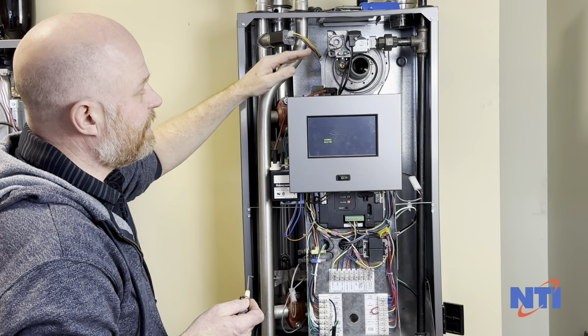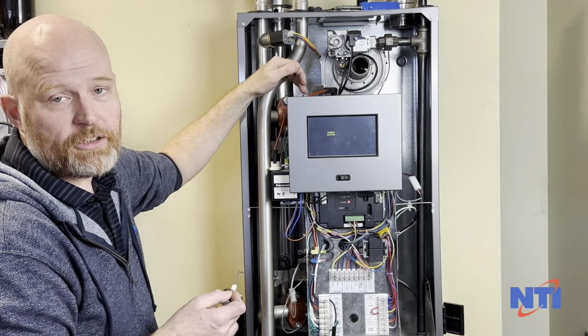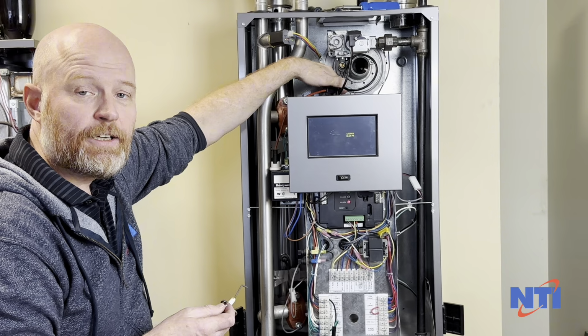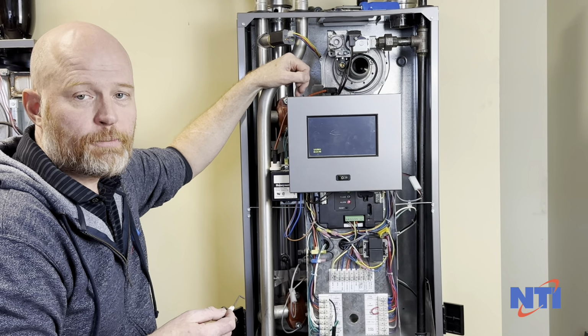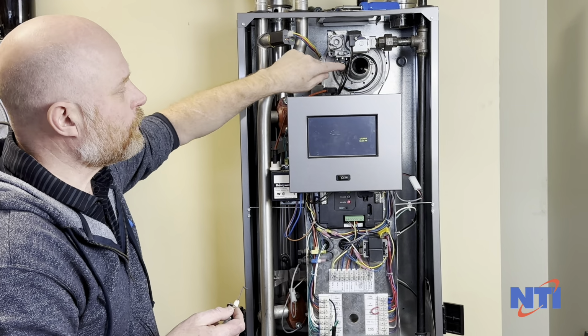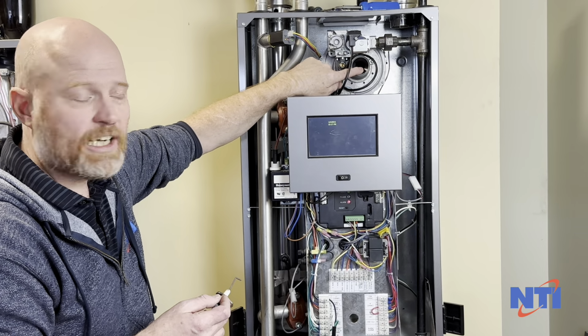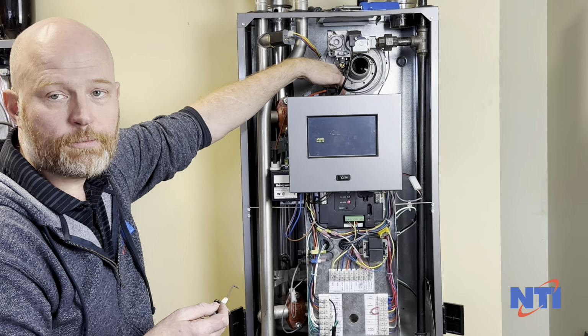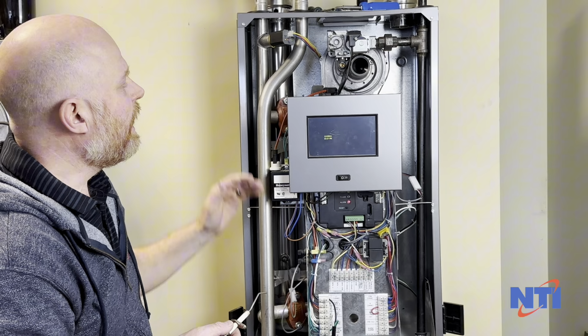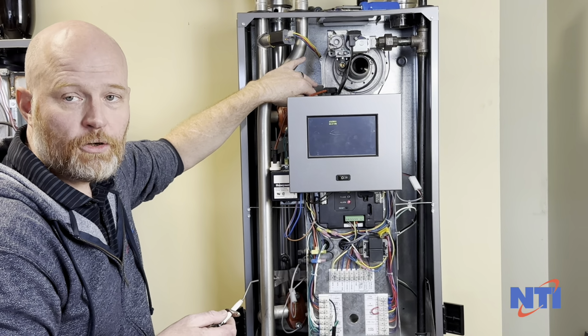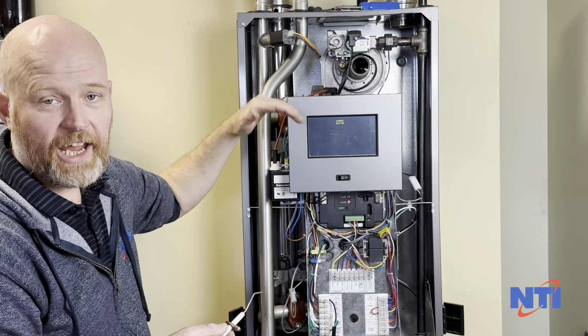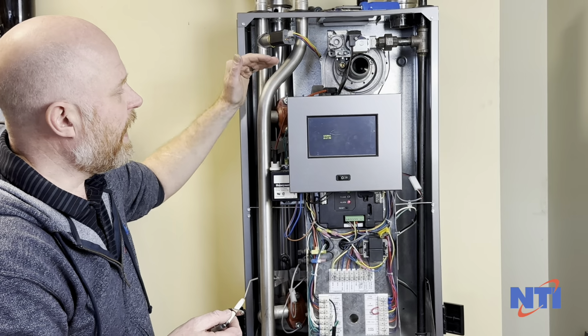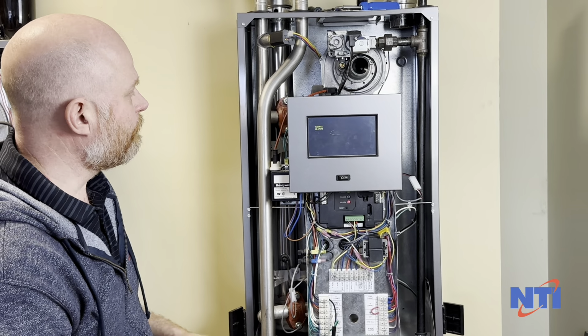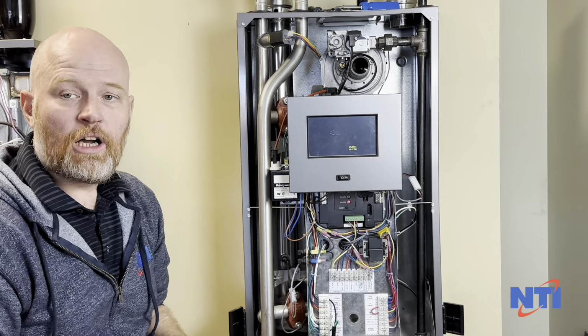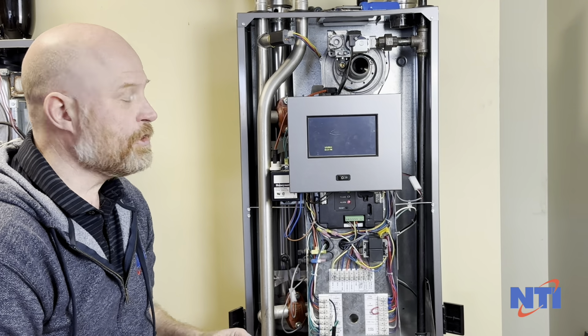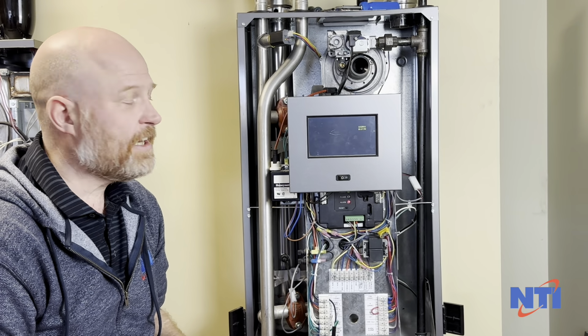If none of that helps, the next thing is going to be to actually open up the combustion chamber, inspect the inside of the burner and the combustion chamber. And you're inspecting inside the burner because any dust and debris and mosquitoes that get sucked in over the years are going to get caught in that burner. They can clog it up from the inside. And of course, the combustion chamber will get dirty over the years, restricting airflow and gas flow through the boiler, and also limiting the ability of the boiler to run. We'll have a separate video on cleaning the TFT boiler. You can view that video on our channel under TFT.